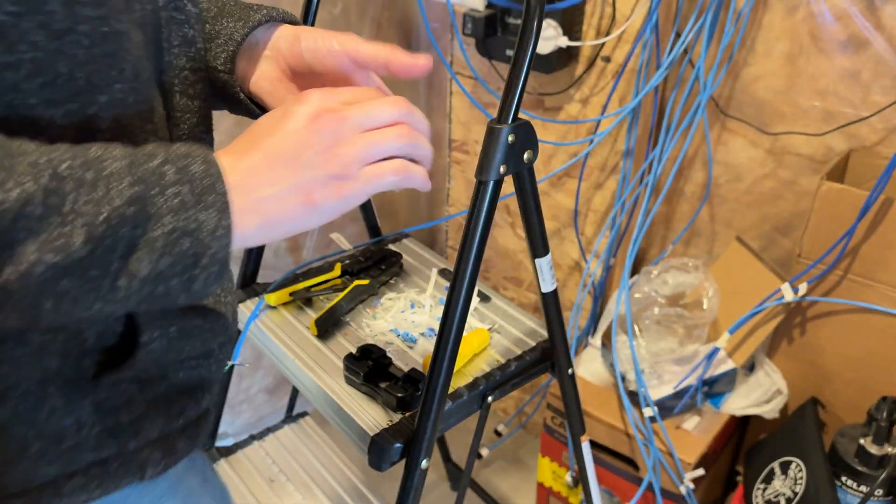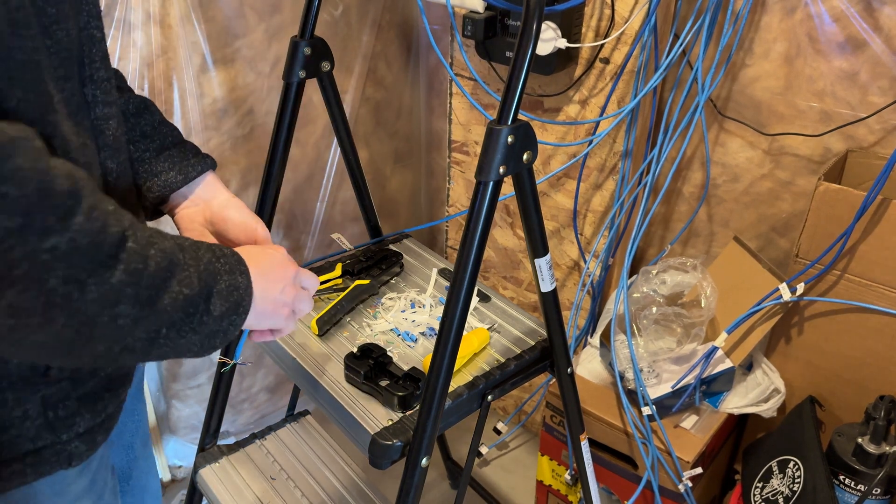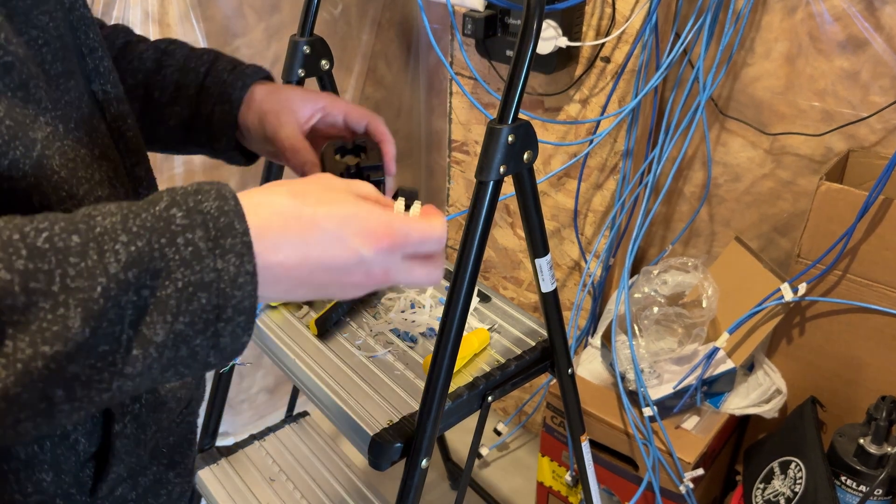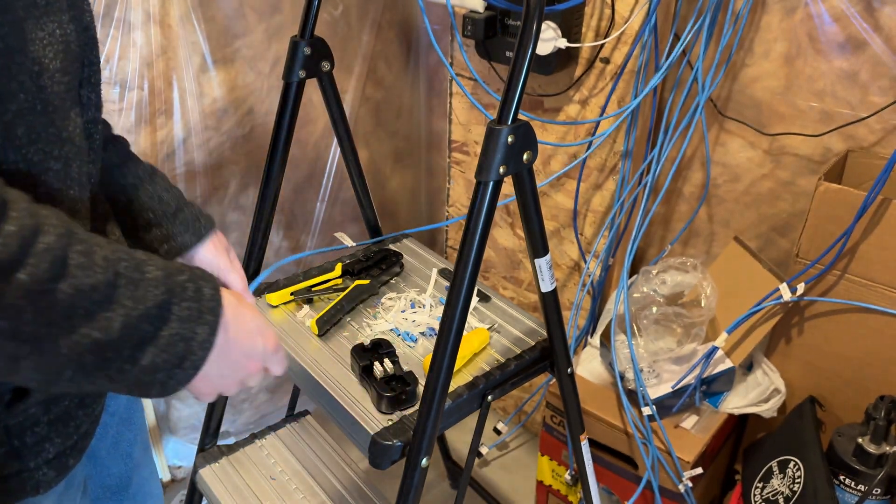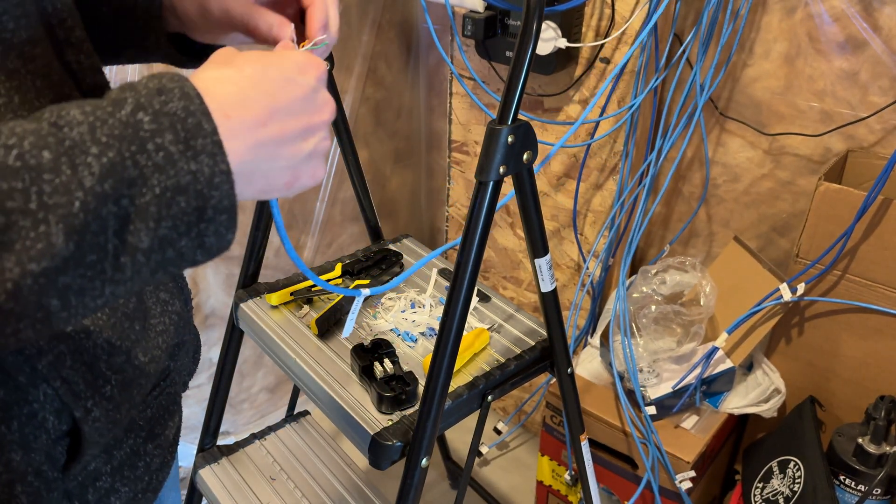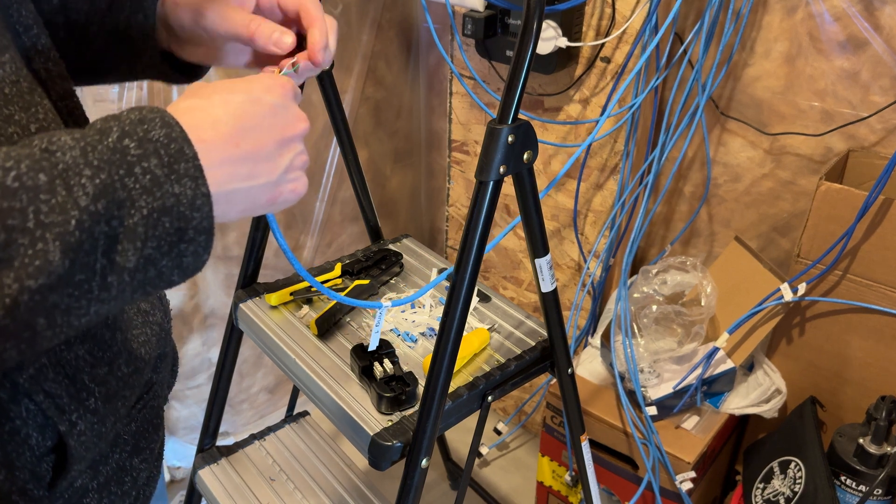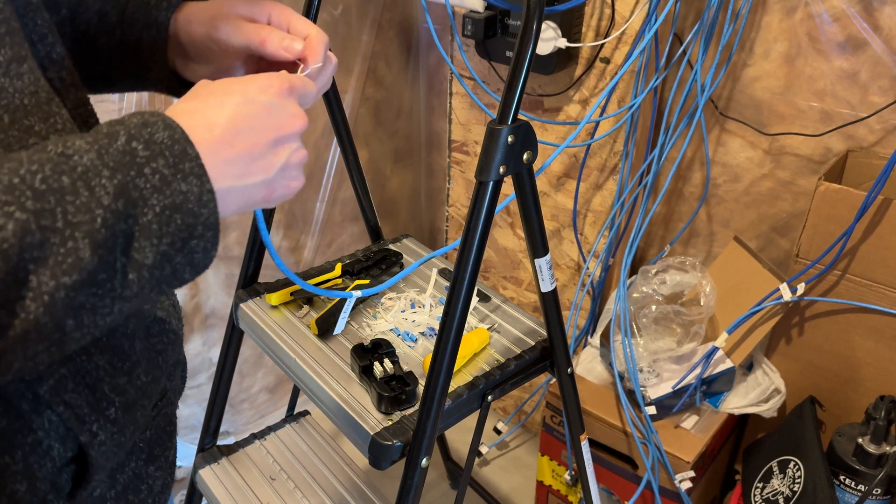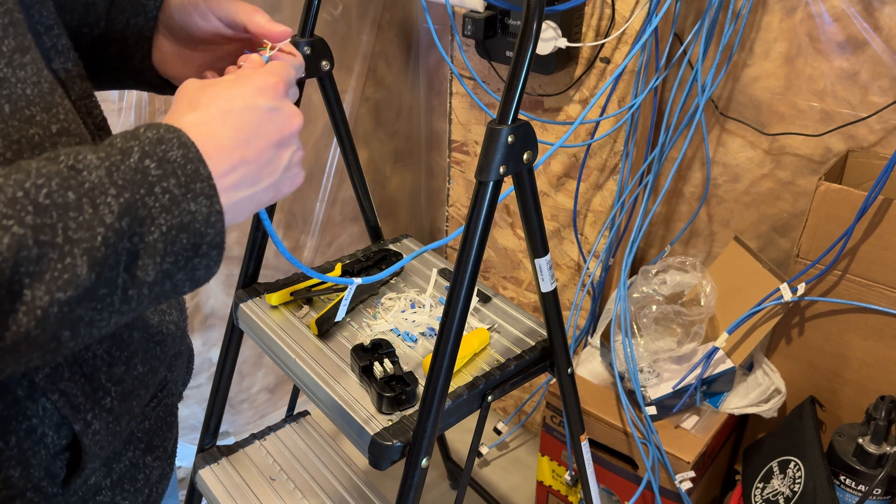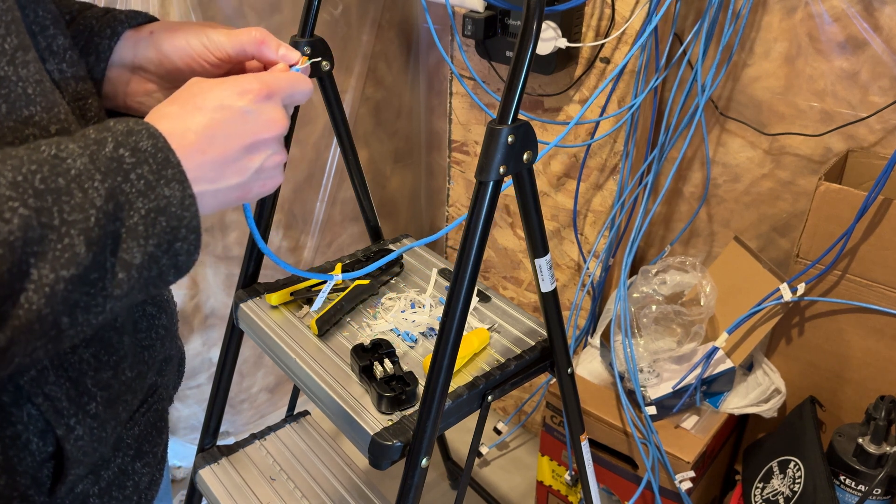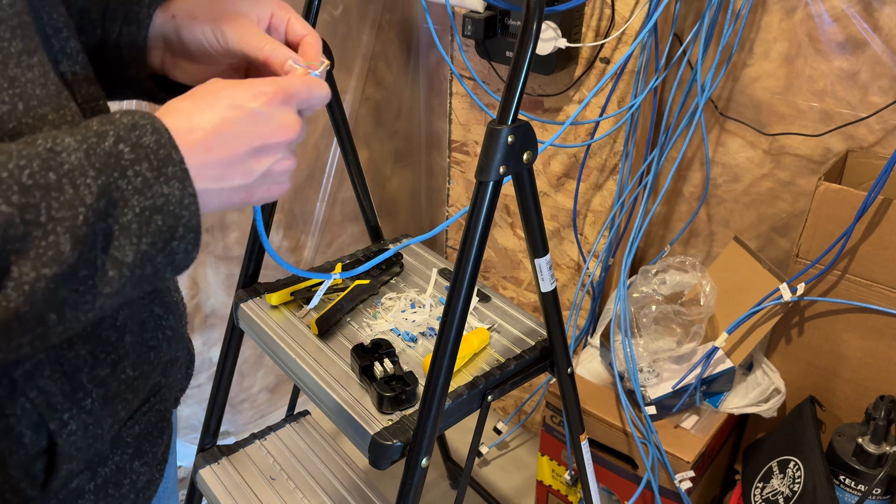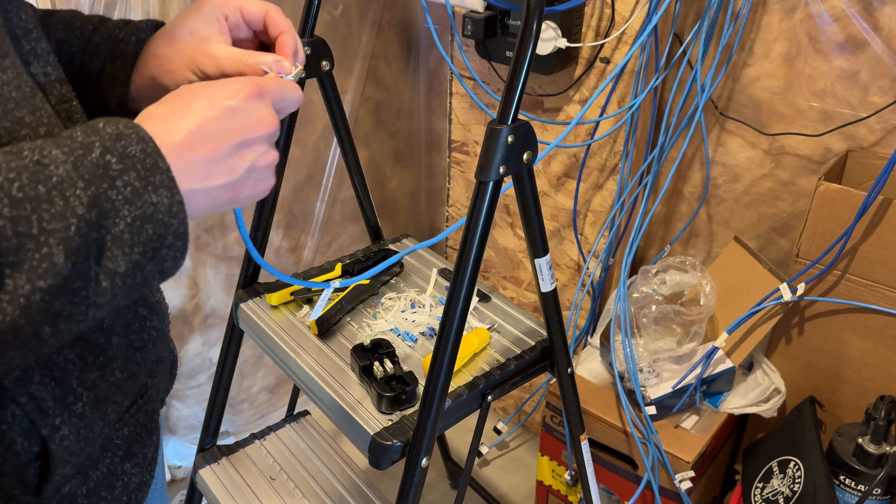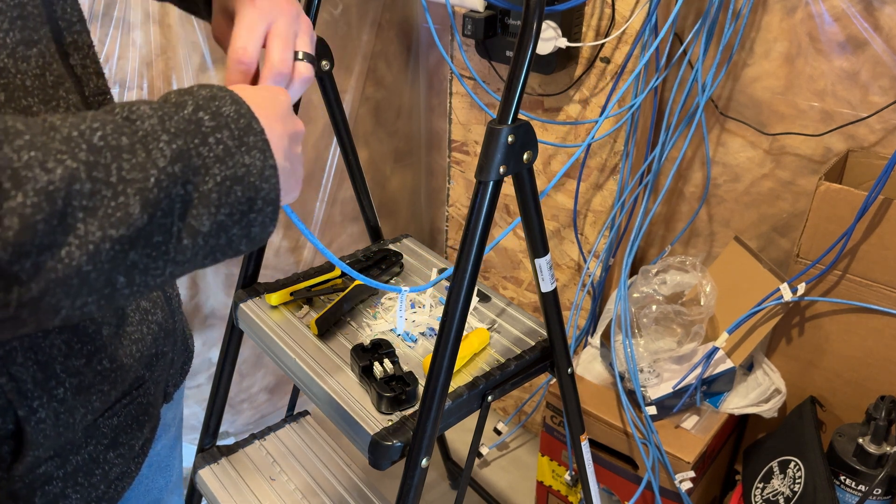Get yourself a keystone. This neat little holder here makes it way easier to deal with. You're going to take your wires. You're going to segment them off based on the standard that you're using. There's an A standard and a B standard. Two different ways to wire it. The cable must be wired the same on both ends. It doesn't matter necessarily which standard you choose. It just has to be the same on both ends of the wire.